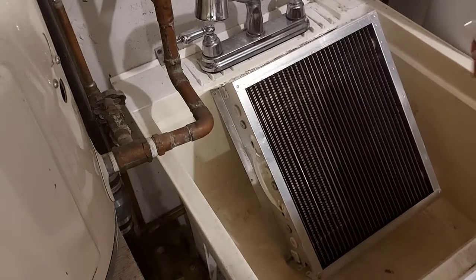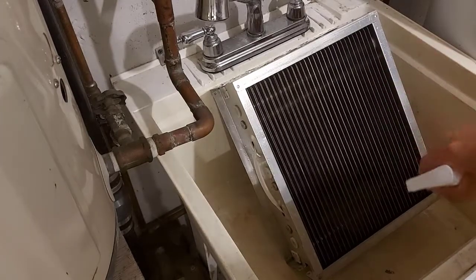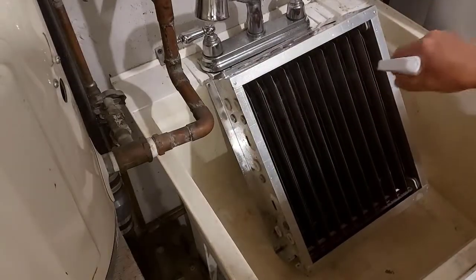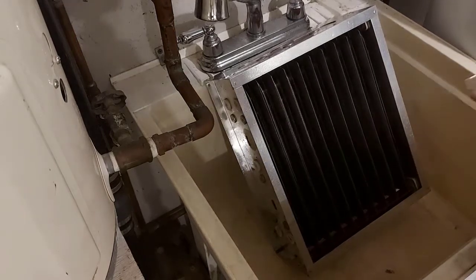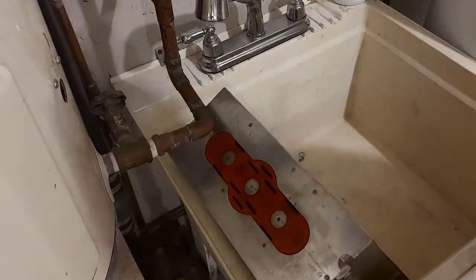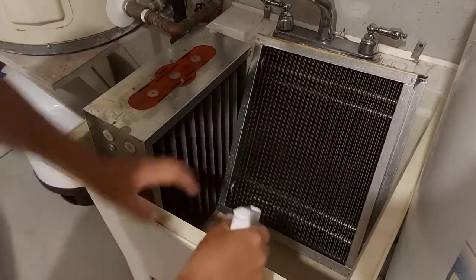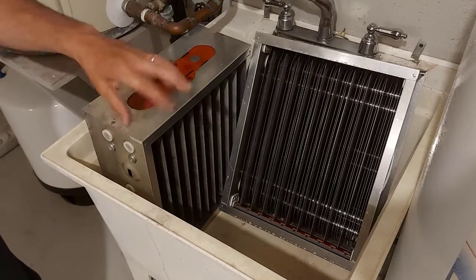We've got the cells in here again and we're going to spray them down with this DAX. This stuff really works well — I'll leave a link below in the description of this video. Spin it around, put it on a 45-degree angle on the short side. We'll move this one to the side and get the other one in. I'll continue spraying this cell. We'll let them sit here now for about 15 minutes and let the DAX soak into them and clean them up really good.